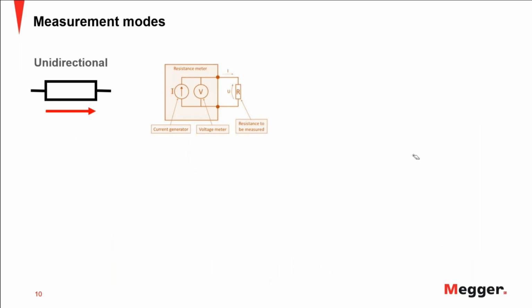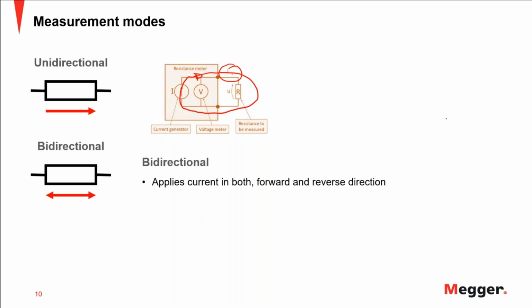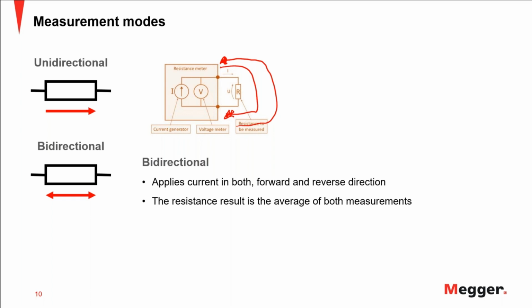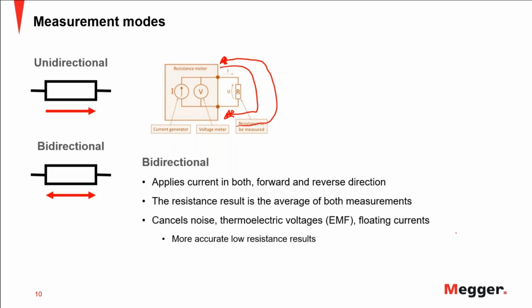Then the measurement modes. We have the unidirectional. So basically, from the initial drawing that I showed, you see the current here, and that current is basically circulating in one direction. So it's doing this, and you get the result. You can also do current injection in one way, and then reverse the polarity of the injection and inject with the opposite polarity. That's what is called bidirectional, applying current in both forward and reverse direction. And the final result is the average of both measurements. What this does is cancel the noise, the thermoelectric voltages, any floating currents, anything that is affecting the result will be eliminated with that. In that way, you only get the actual value of the resistance that you are intending to measure.